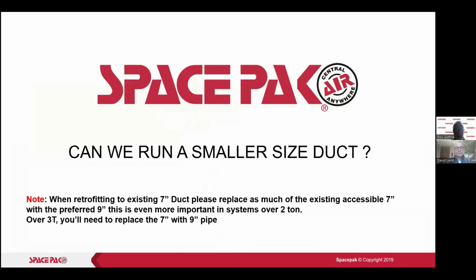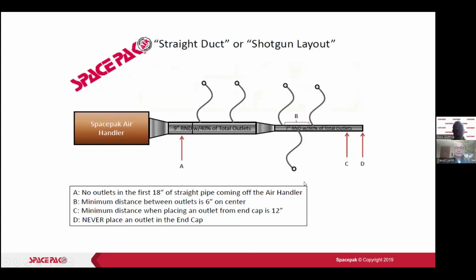Can we use a smaller size duct? We get asked this a lot because older systems used 30% less CFM than we use today. So today we use 9-inch duct, and back then they used 7-inch duct. In the retrofit section, you'll find these in the installation manual, and there's one for download as well.